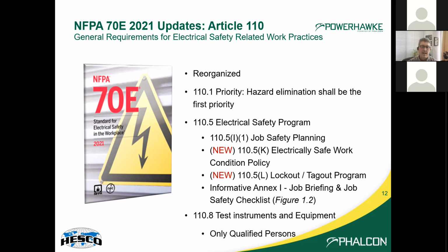This last point, 110.8, really should have been understood, but they made it explicit that only qualified persons should be using test instruments and equipment. Voltage testers and meters are not for a casual user. You should have proper PPE and shock protection. A person who isn't properly qualified may not understand the limitations of the test device in their hand. Test devices are rated, and testing a 1,000-volt circuit with a 600-volt rated piece of equipment is a recipe for disaster. So again, only qualified persons should be involved in anything having to do with energized circuits, including testing those circuits.